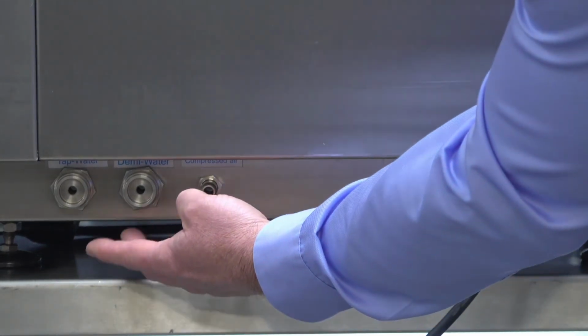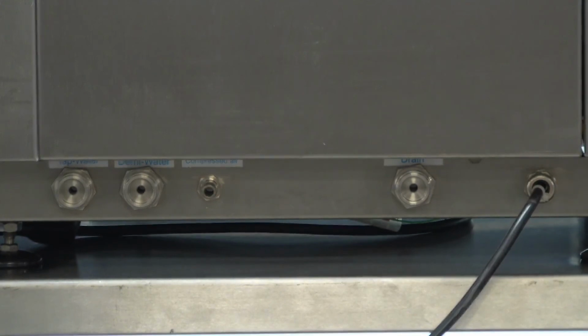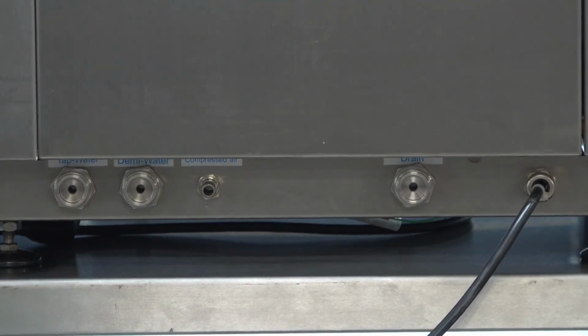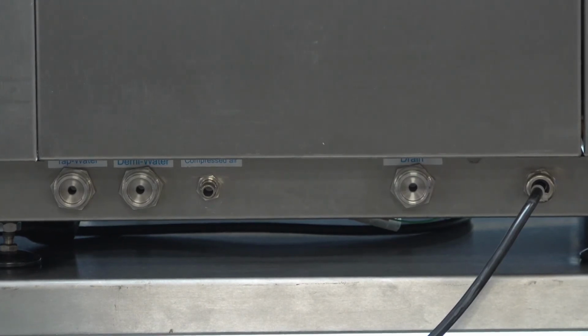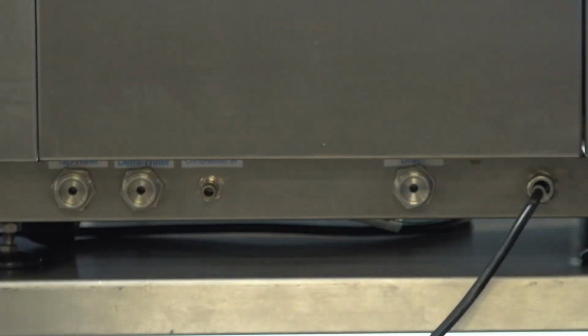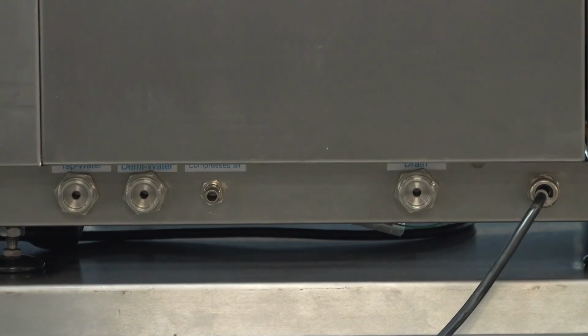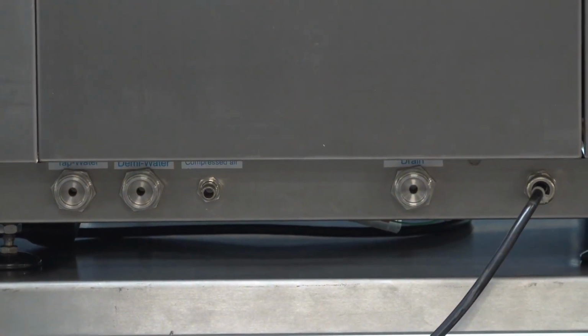Next thing we have is a demineralized water. If you do not have hard-fed demineralized water, we also offer a demineralization system that we can also run directly with the unit. They're both very small. They would set even under this 65. They would set right there and just operate straight away. So the demineralization system would just plug into your tap water, and then we would just run two different taps. We would plug right into the tap water. Tap water is going to be used for cooling. Then in this case, we would run it to our demineralization system and then run it to the demineralized water for that. So those are the requirements. You would have demineralized water, tap water, a drain, compressed air, and then your power requirement as well.